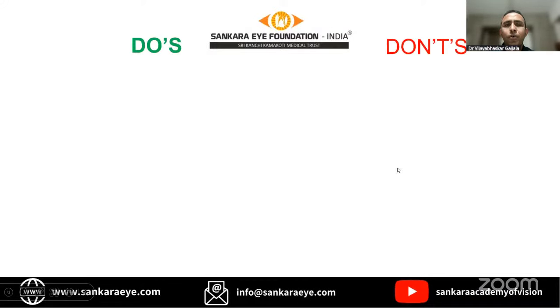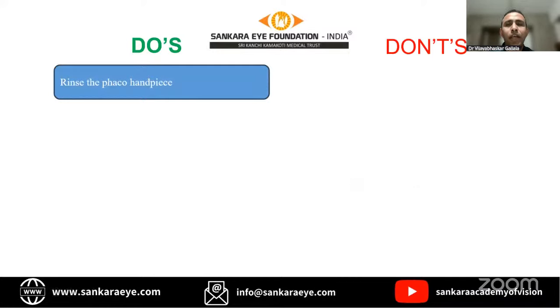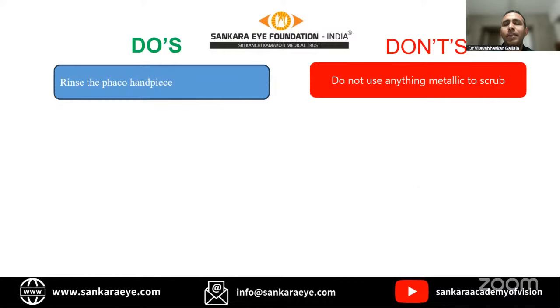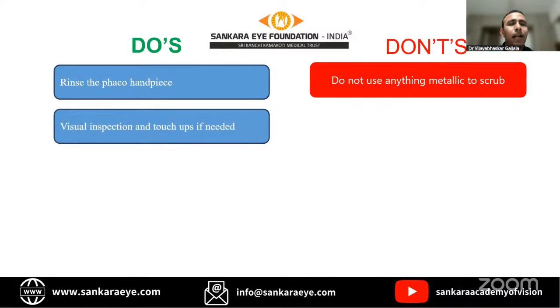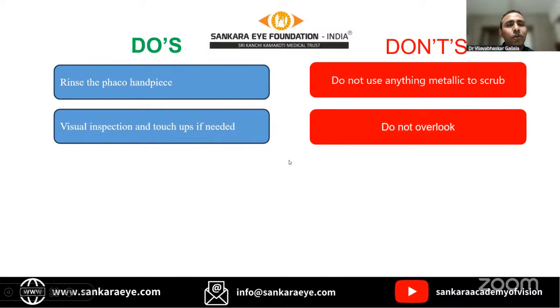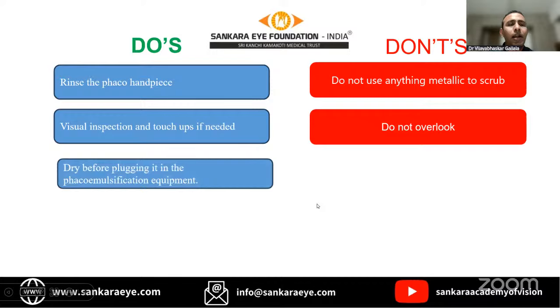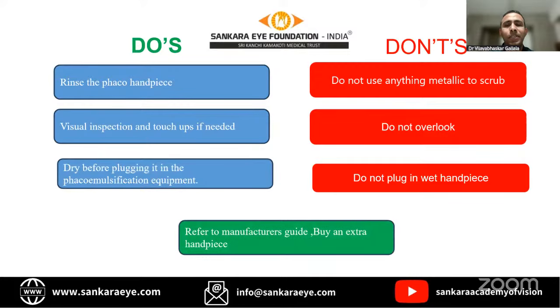So what are the do's and don'ts when you are cleaning the phaco and other instruments? To rinse the phaco handpiece, you should not use any metallic brush to clean it. Visual inspection and touch-ups are needed, and do not overlook this, not only for the phaco handpiece, for every instrument it is important. And dry before plugging it into the phaco emulsification equipment. You should not use a wet handpiece directly. So refer to the manufacturer guide.